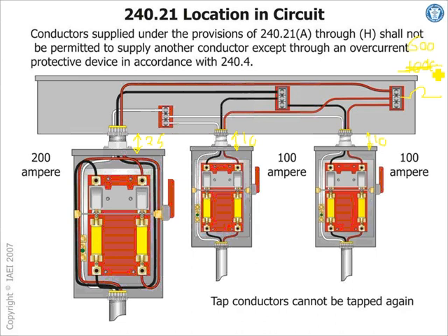But I'm tapping 100. It's okay. No, there's no problem with that. I can size my feeder for 100 now. So the minimum conductor that you can tap is 60. Can I tap 100 conductor amp? Yeah, no problem. What's the decisive factor? How about if it's 1,000? I keep going up, right? What's the decisive factor here?